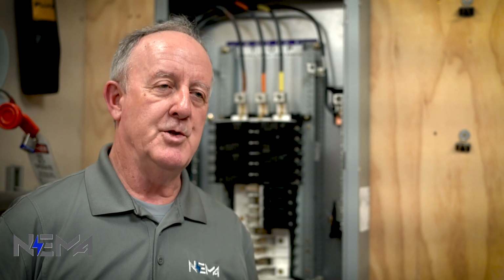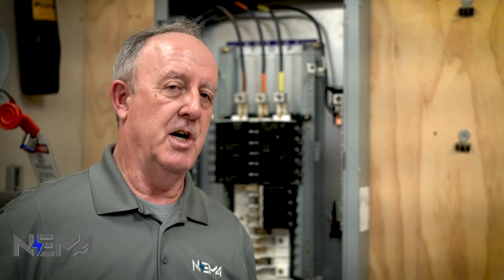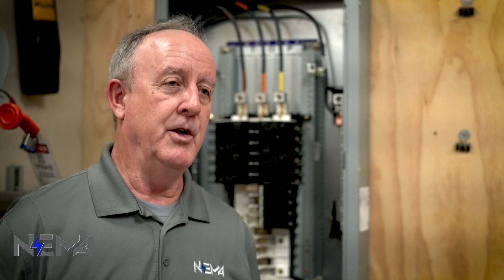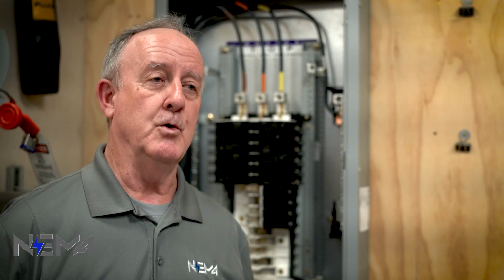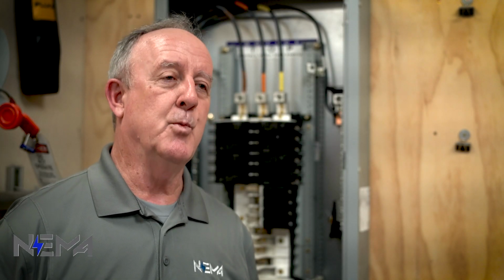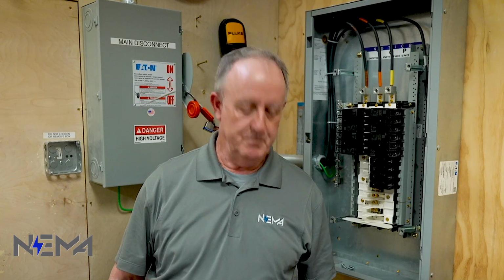So why use the torque measuring tool in the first place? Why can't I just tighten it up to where it feels good and tight and call it a day? Well, about 90% of electrical failures occur at termination points. They burn up, the conductors burn up, the equipment can fail. And so it's very important that the initial installation is done correctly to the proper torques. And it can take months or years or sometimes even decades for those failures to occur. And they can be caused by having improper torque values at the initial installation.